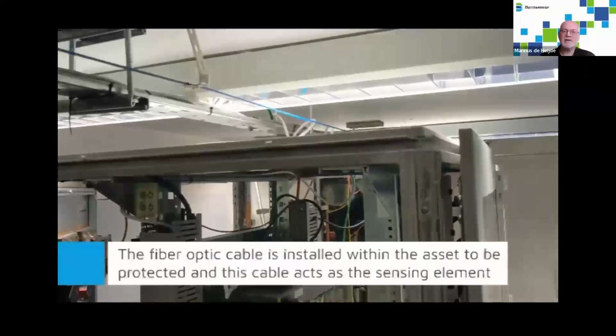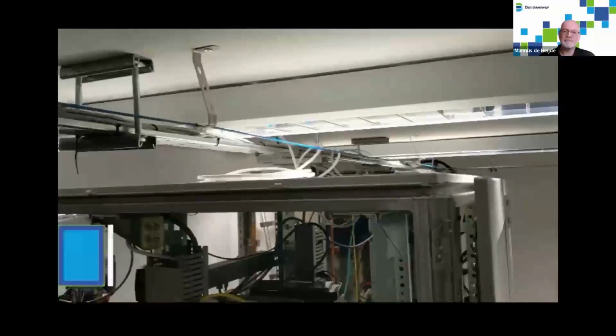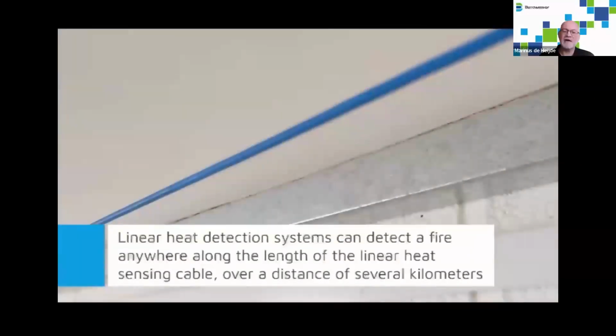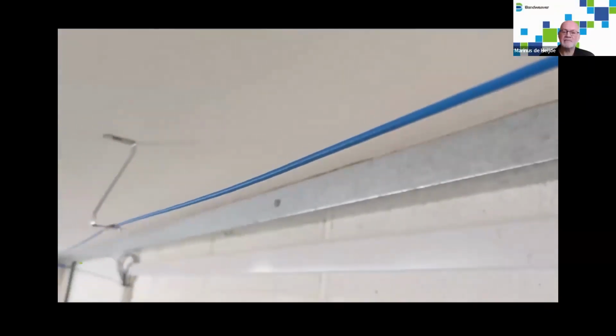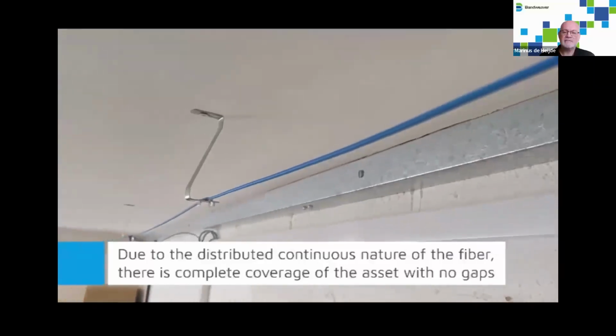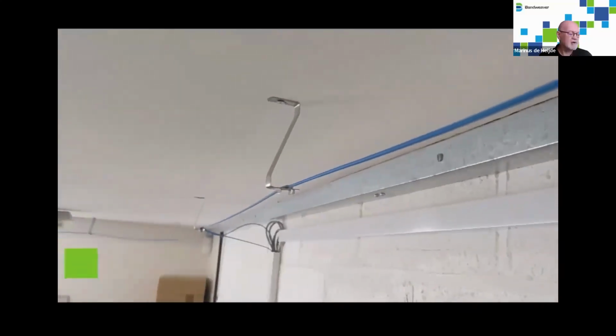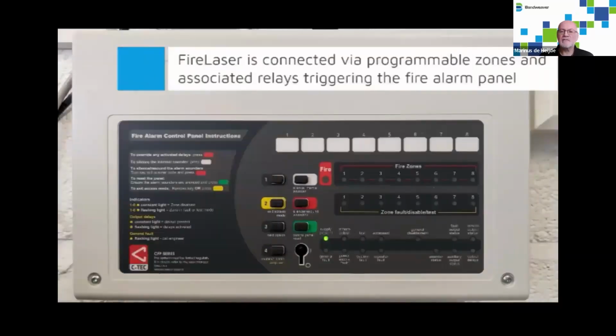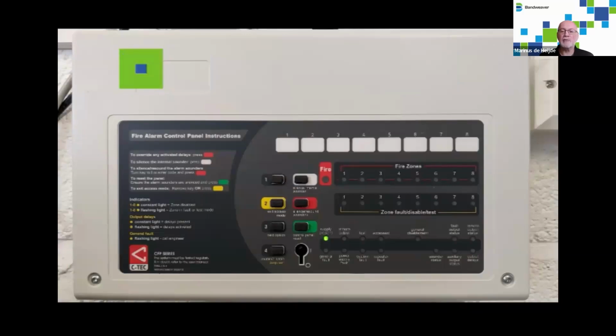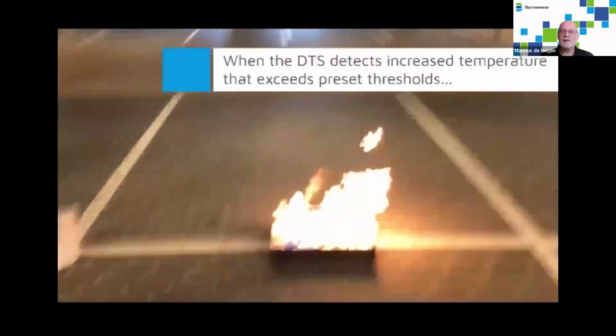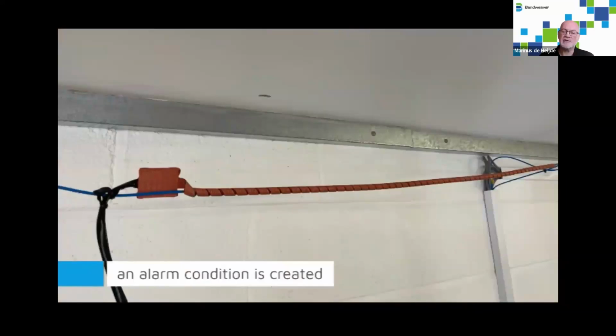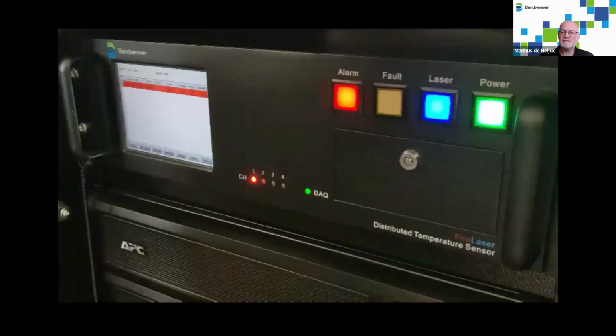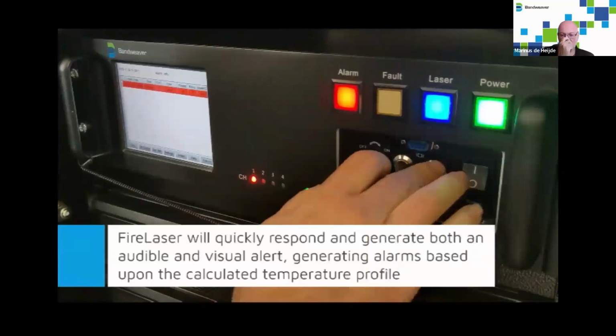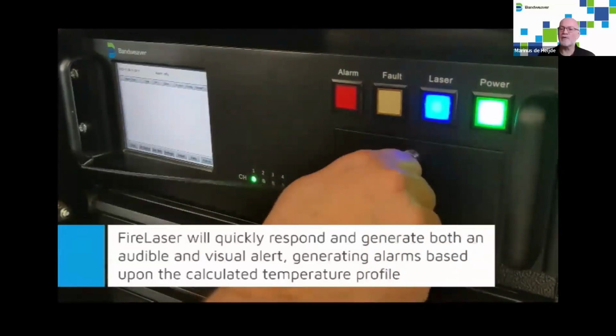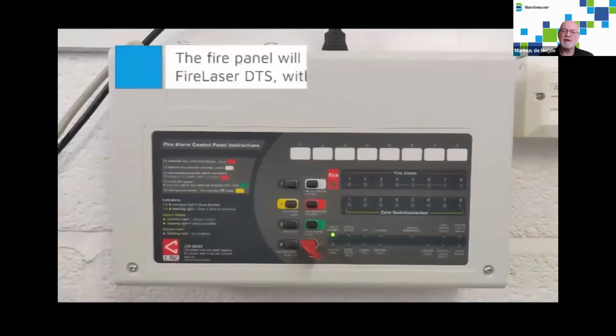The fiber optic cable, this is an example of an installation in a building where the cable is near the ceiling. We can detect the fire anywhere along the length of the LHD cable. Again, there is complete coverage of the assets with no gaps. We're also connected via relays to a fire control panel. When we detect an increased temperature that exceeds the alarm thresholds, an alarm condition is created. It generates an alarm based on the calculated temperature profile, and then we can reset the alarm.